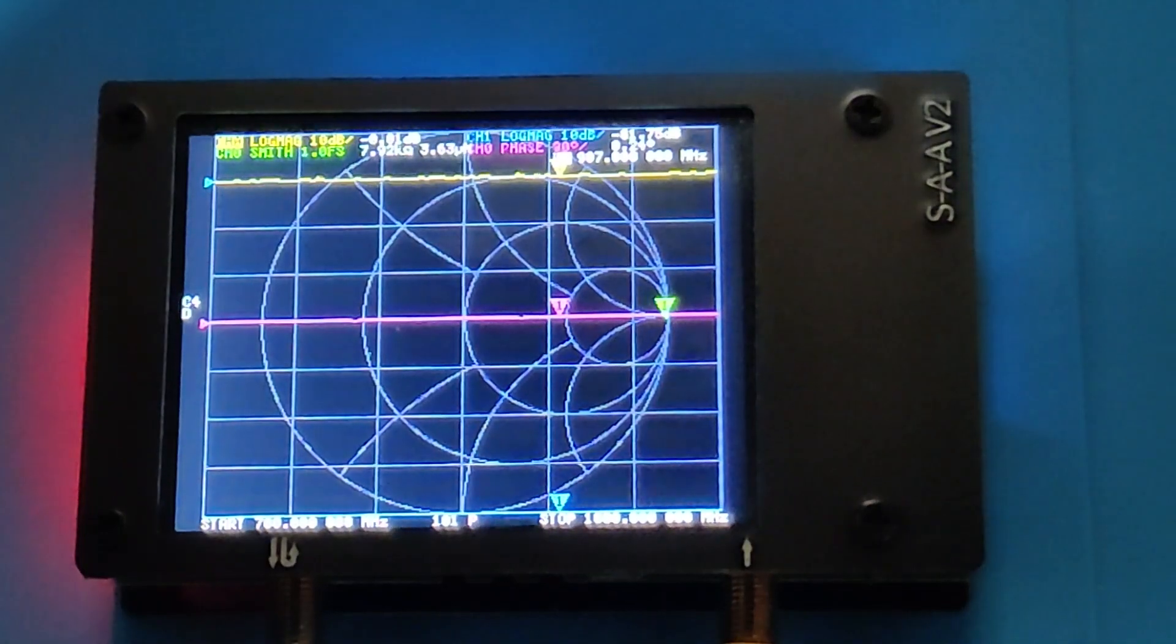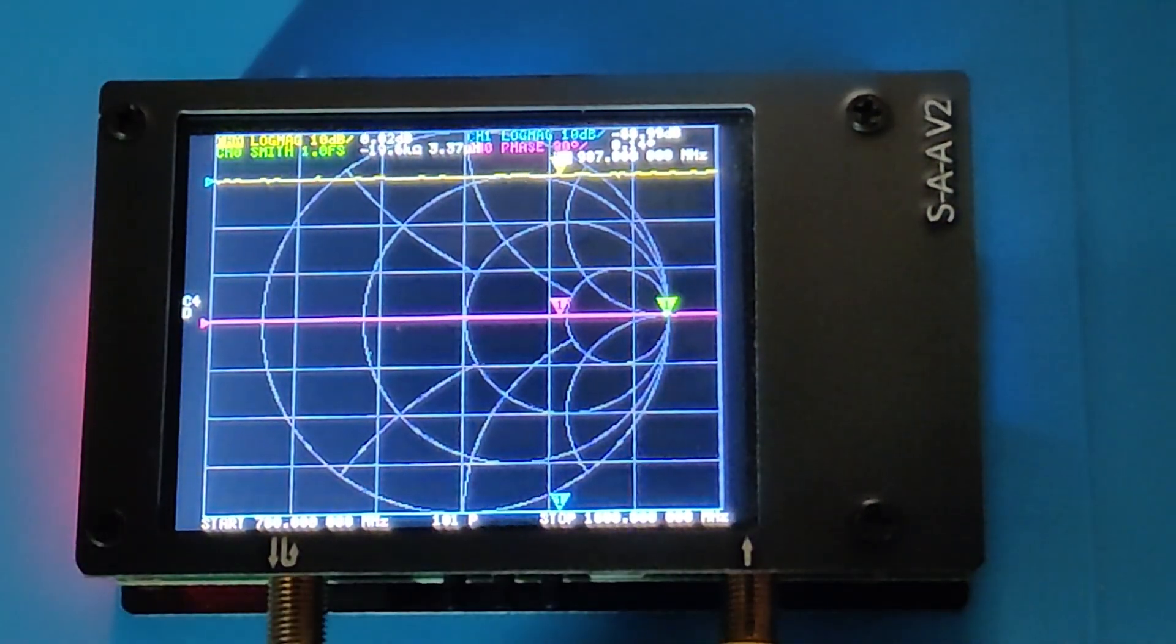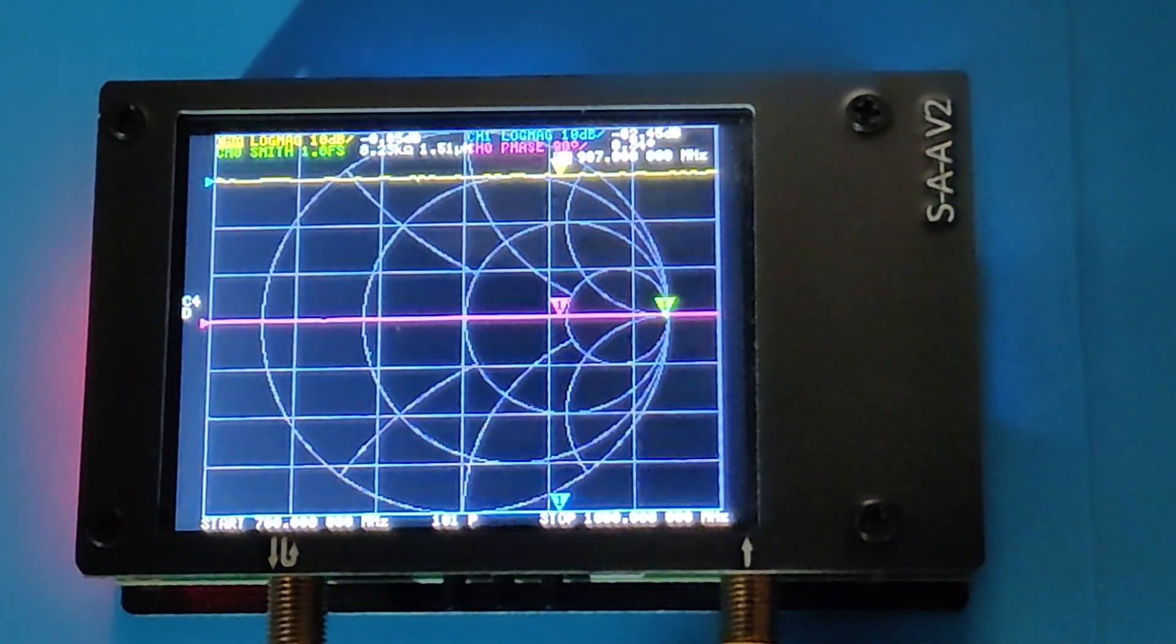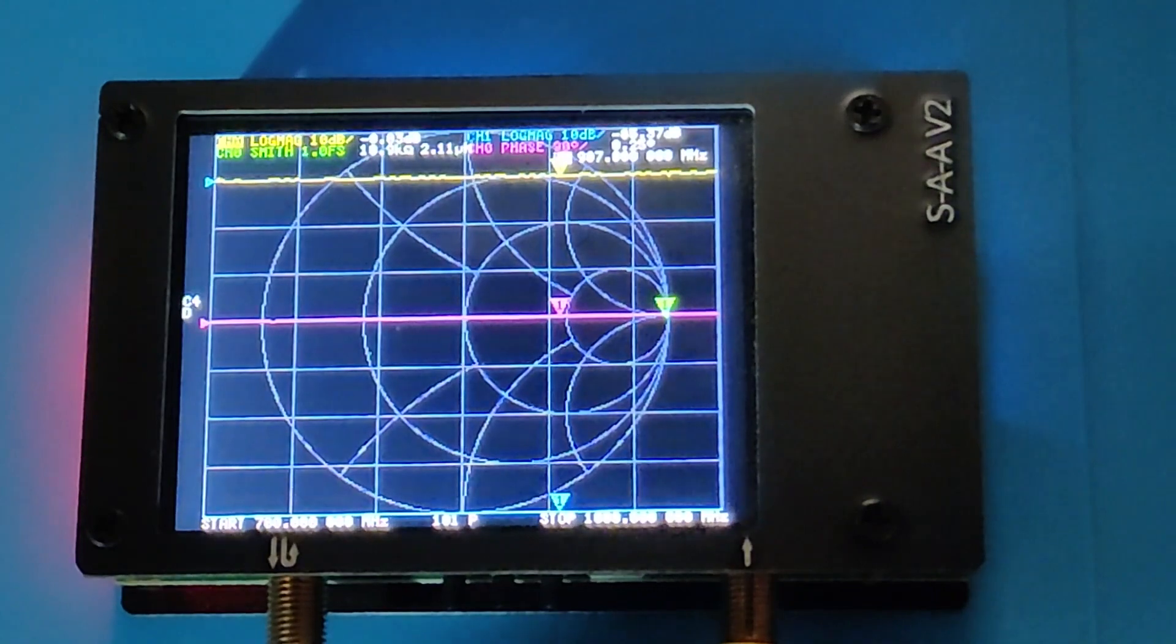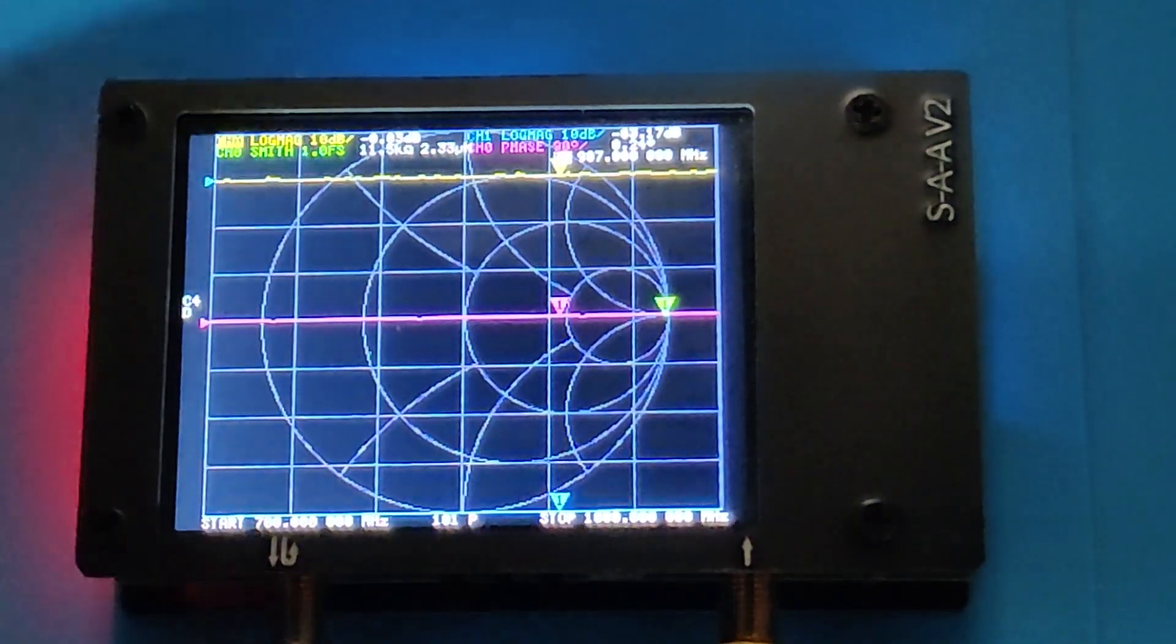So the VNA will load all the calibration and all other settings into the memory now. We can verify by looking at the start and stop frequencies. To verify it further...